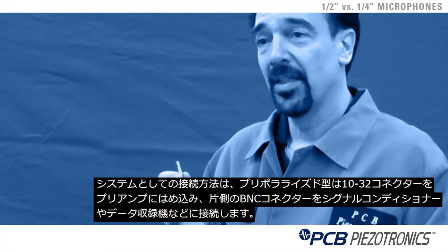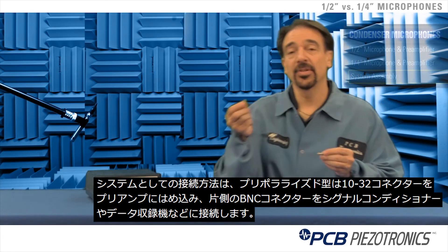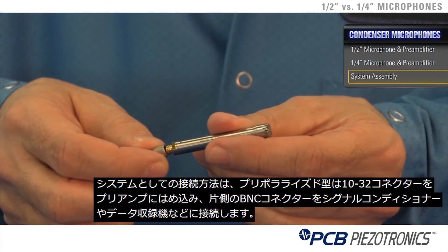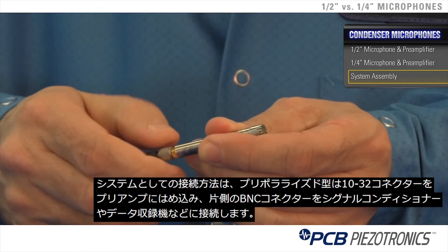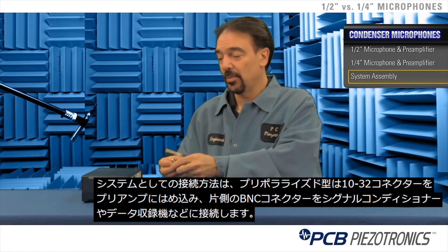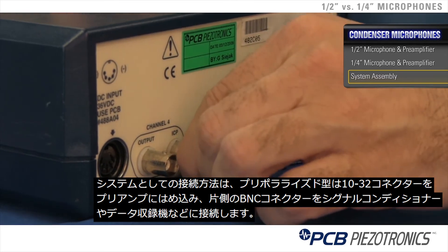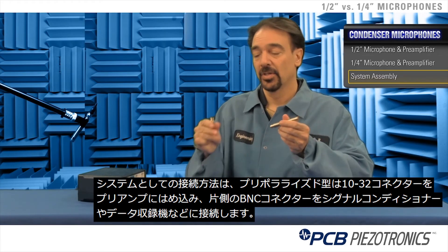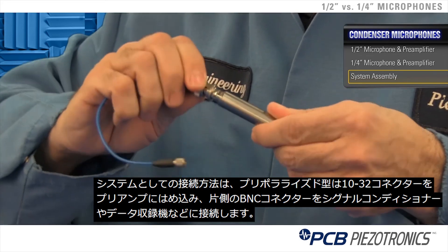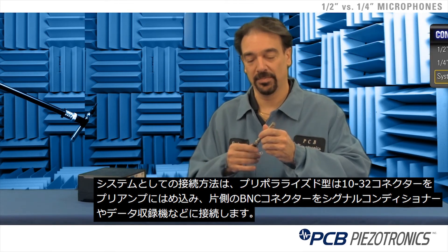The pre-polarized design takes a 10-32 micro dot connector that screws into the preamp, and then a BNC connector on the other end typically goes into your signal conditioner or data acquisition system. Your half inch microphone terminates in a BNC connector, so you would have a BNC to BNC connection, with the end terminating cable also BNC to go to your signal conditioner or data acquisition system.